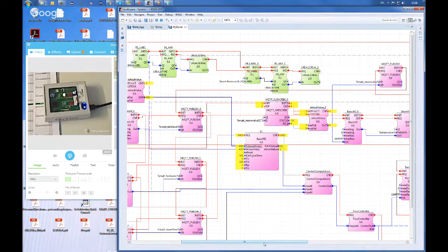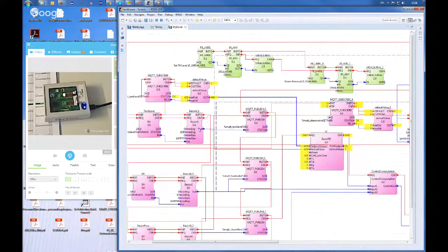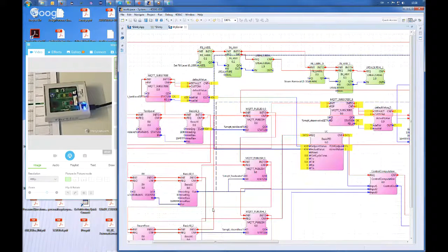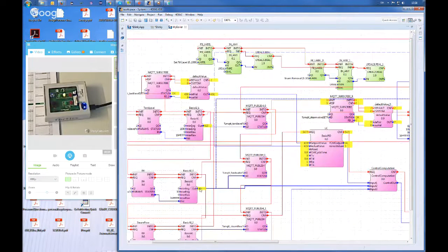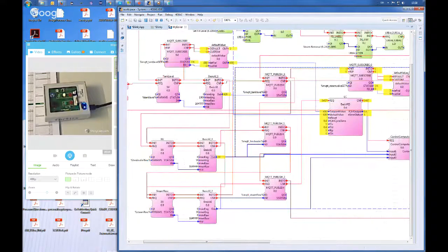The reason is mainly that we have some noise in our measurements, and we have some pressure problems in this tank. And this is the feed water flow. You see here the feed water is flowing a lot, the tank level is jumping around a bit.